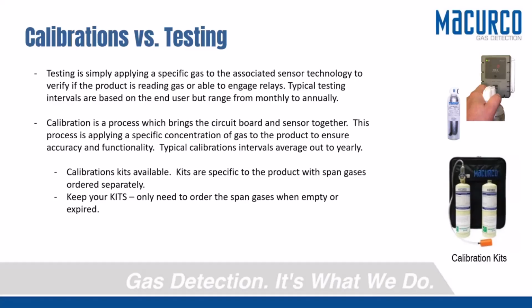And so a calibration is basically marrying the sensor and the circuit board together to read a very similar number. It's plus or minus 5% from a variance. But at the end of the day, we want that sensor to be reading 5 ppm of NO2, and the circuit board's saying, okay, well, that is 5 to me as well. And that's what it's interpreting to the panel or to whatever system it's tied to.